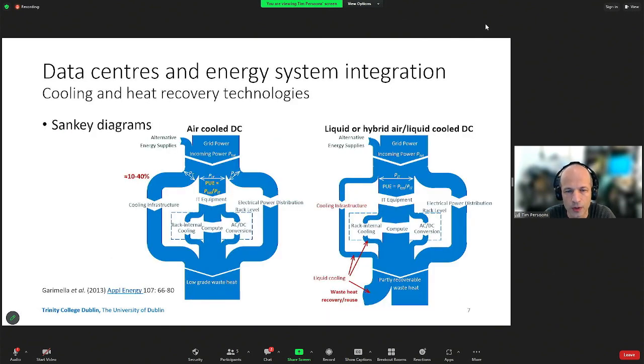So schematically, a Sankey diagram would show where the energy flows are in a typical data center. On the left here, you have an air-cooled data center, and a metric that you may be familiar with if you read literature on data centers is the so-called power utilization effectiveness, or the PUE factor, which is essentially the ratio of the total power consumption of the system divided by the power consumed just by the IT equipment. Right, and then in addition, you have the cooling infrastructure, which in an air-cooled data center can be anywhere up to 30-40% of the total power consumption, depending on the type, right? But then all of that energy effectively is dumped in the form of low-grade waste heat in the atmosphere.